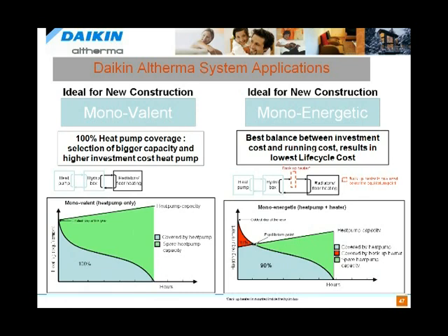where we'll size a system where it will have 90 to, in our Mediterranean zones, maybe 95 to 97% of the load managed by the heat pump without any backup. And the electric element will be used 3, 4, 5, maybe up to 10% of the time to meet extraordinary peak load requirements in, let's call it December, for heating.